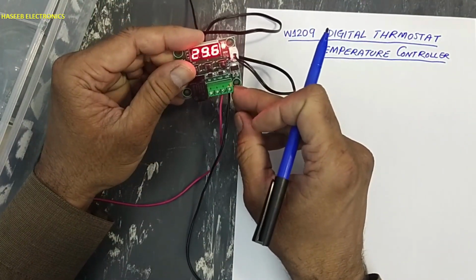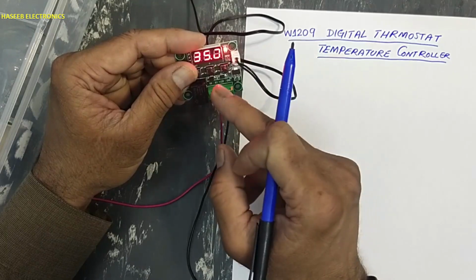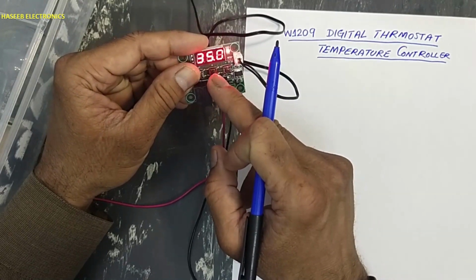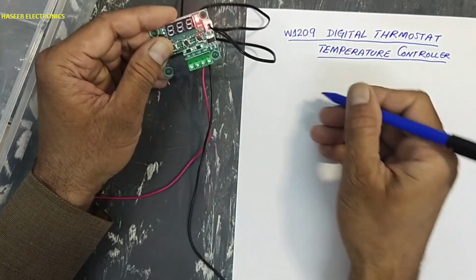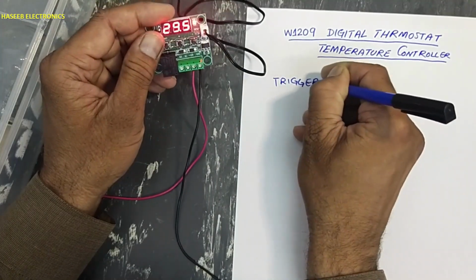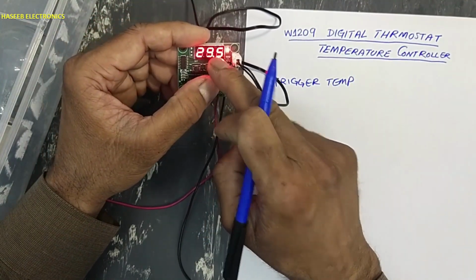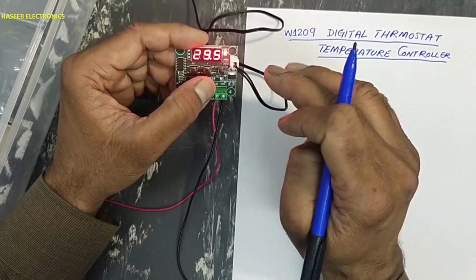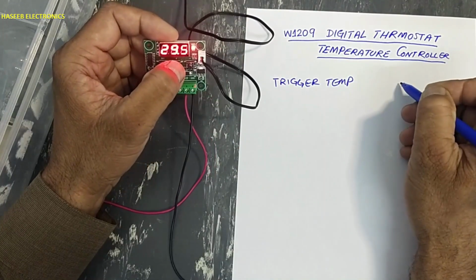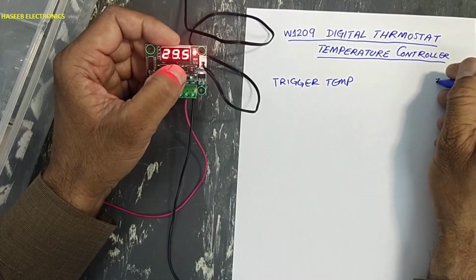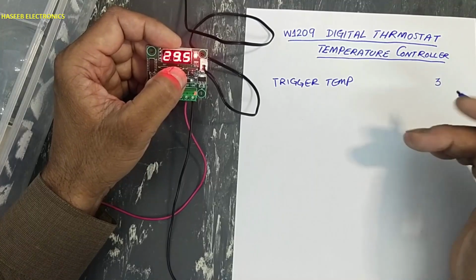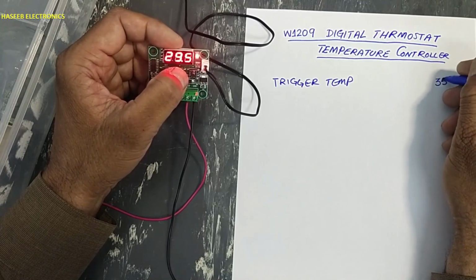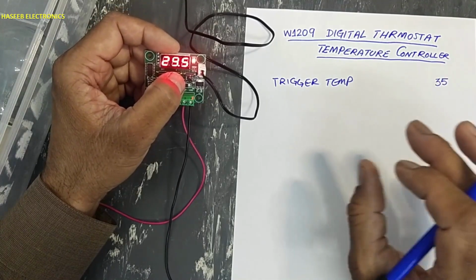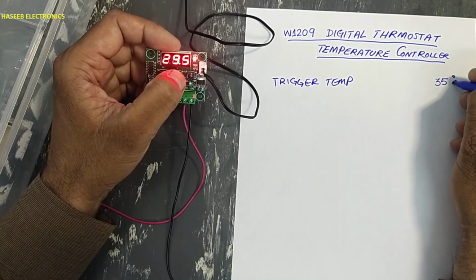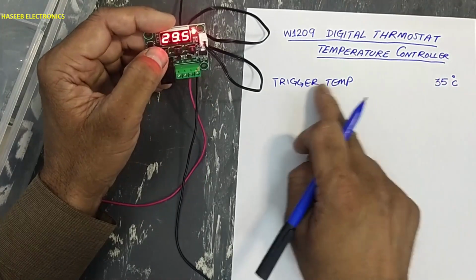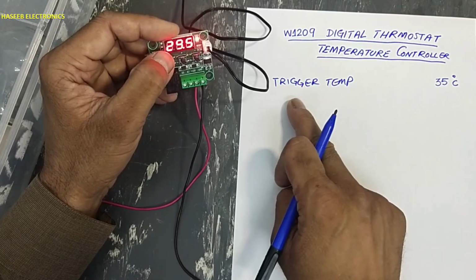If I press the set button, there is a flashing indication that is 35. It is the trigger temperature. We will set this temperature for our requirement. If we are using heater mode, for example, I want to obtain maximum 35 degrees Celsius.